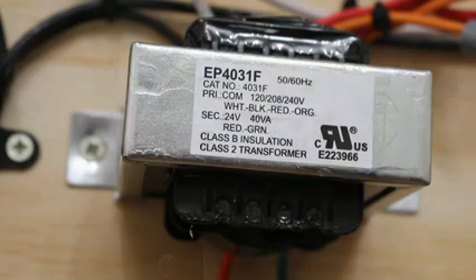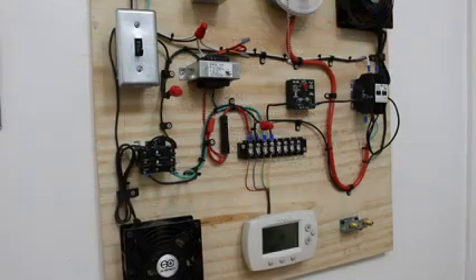I'm going to start off with the easiest and fastest way to check if your transformer is operating. The way to check that is to make sure you have your secondary voltage. The easiest place I would say to check for that is behind your thermostat. You're going to have a constant 24 volt supply between your R and C terminal. Instead of climbing into crazy places, going into attics, running outside, and taking off all these panels, the easiest and fastest way would be to go straight for your thermostat.